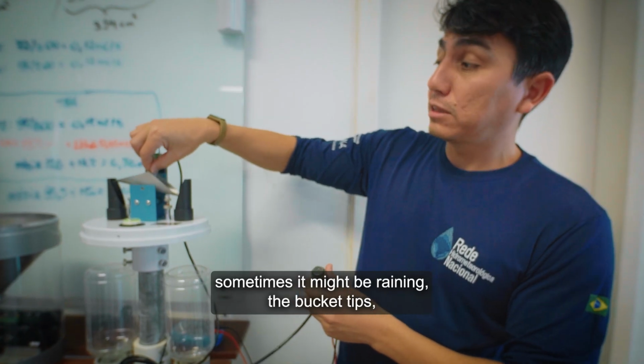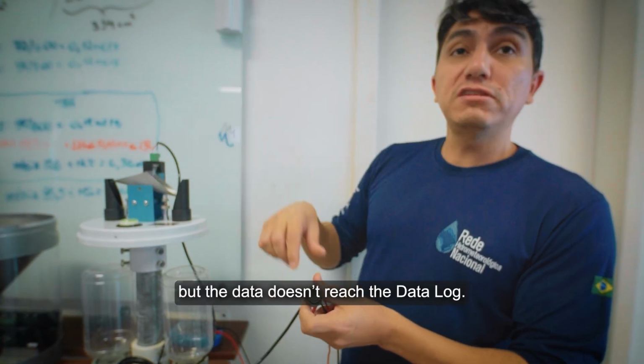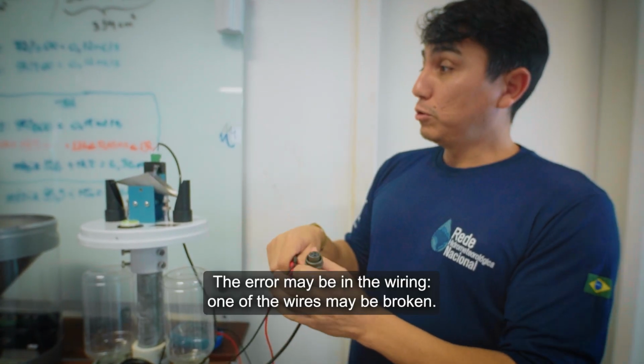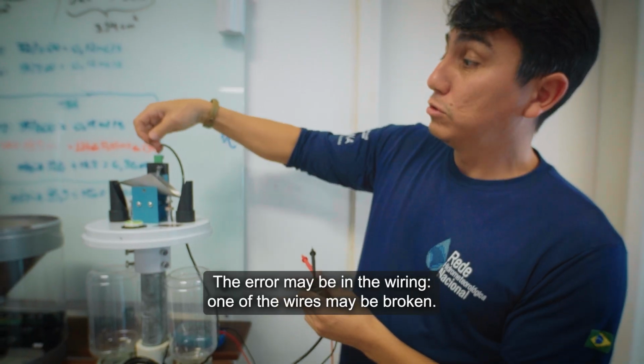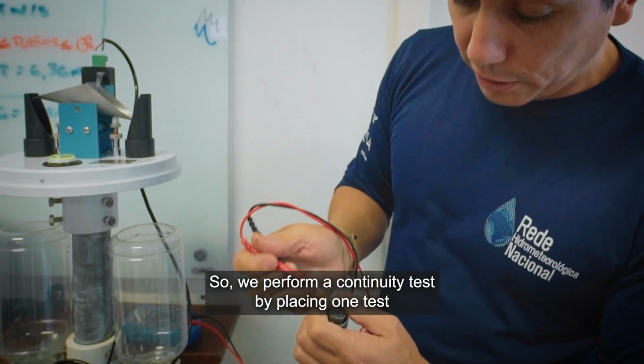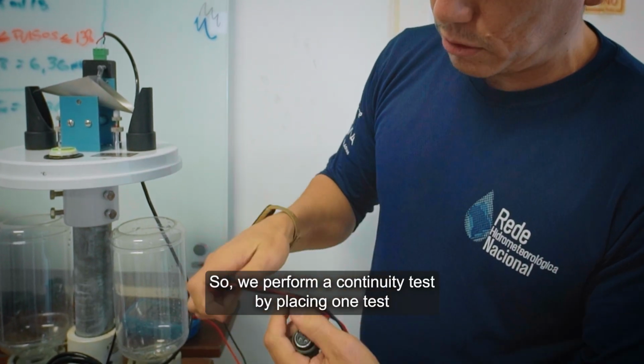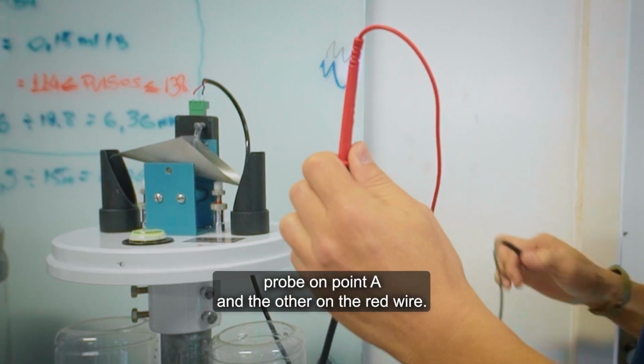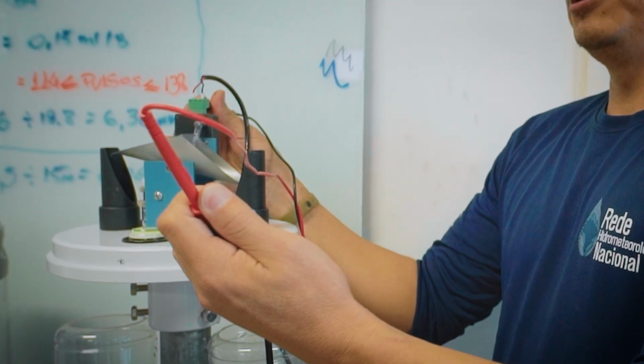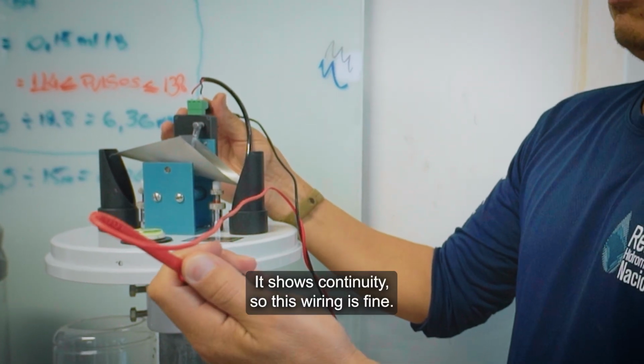Sometimes it might be raining, the bucket tips, but the data doesn't reach the data log. The error may be in the wiring. One of the wires may be broken. So, we perform a continuity test by placing one test probe on point A and the other on the red wire. It shows continuity, so this wiring is fine.